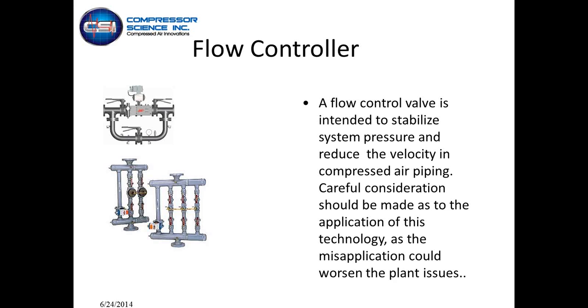Flow control valves, there's been a lot of talk about flow control valves over the years, whether they're good, whether they're bad, whether you need one, whether you don't need one because you can use a VFD. When we look at large distribution systems that have a myriad of piping, and I'm talking about plants that are 300,000, 400,000, 500,000 square feet, and the compressor room is centralized at one end of the building, you have a transducer on each compressor that is designed to control what's going on in the piping system that's at the other end of the plant.